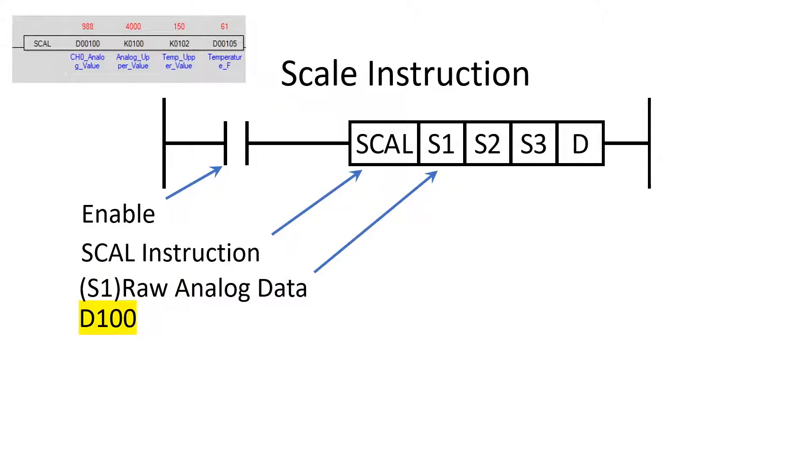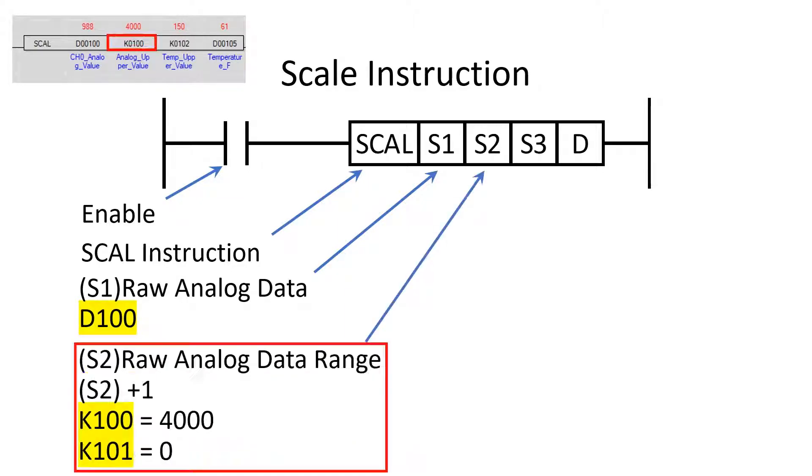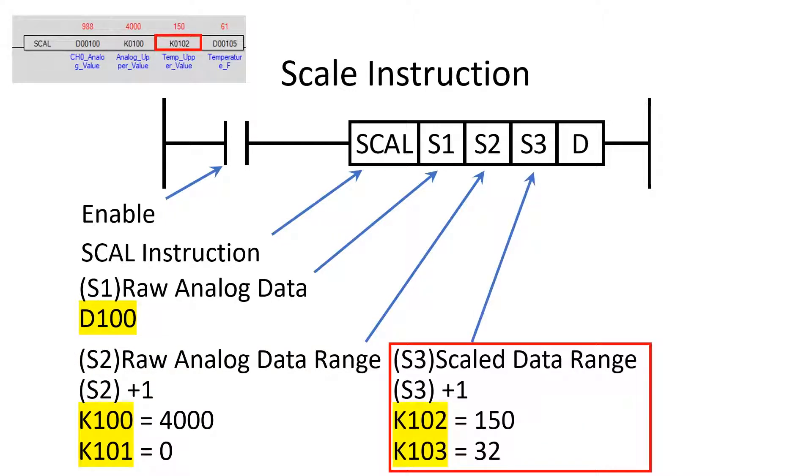Operands S2 and S3 are stored in K memory as this is retentive memory. The S2 operand is the memory location of the upper value of the raw analog range. This analog channel is set up with a max count value of 4000. S2 plus 1 is the memory location for the lower value of the raw analog range. The S2 locations are K100 and K101 for the range of 0 to 4000 counts.